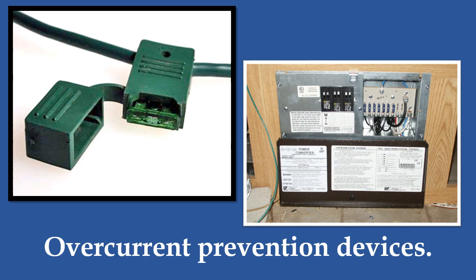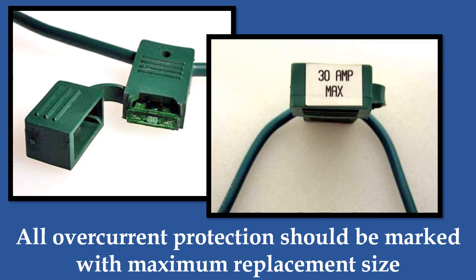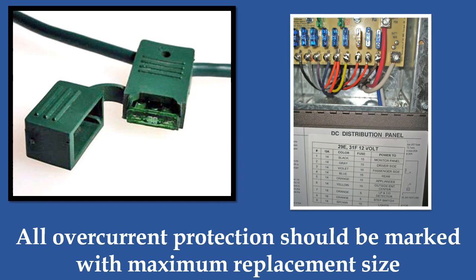Combination load centers, seen here on the right, house both the 120 volt breakers and the fuses for the 12 volt system. In many cases, 12 volt converters are part of a combination load center. Blade type fuse holders must be marked with the maximum replacement size. This can be done either on the fuse holder itself, as seen here, or in labeling attached adjacent to the wires being protected. With combination load centers, labeling of the replacement fuse size is normally found printed on the door of the load center housing.